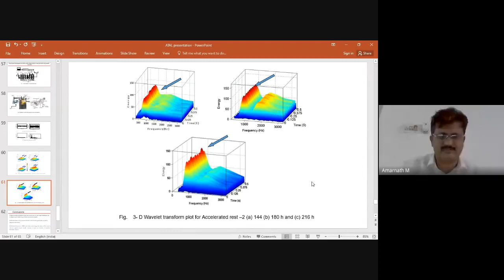So I have developed some low cost test rigs, because some MNC companies are charging too high, lakhs of rupees. The same test rigs you can fabricate in your laboratory with minimum funds, below 50,000. You can have a good condition monitoring test rig. There is a roller bearing test rig, oil lubricated or grease lubricated bearing test rig. The cost is around 30 to 40,000.